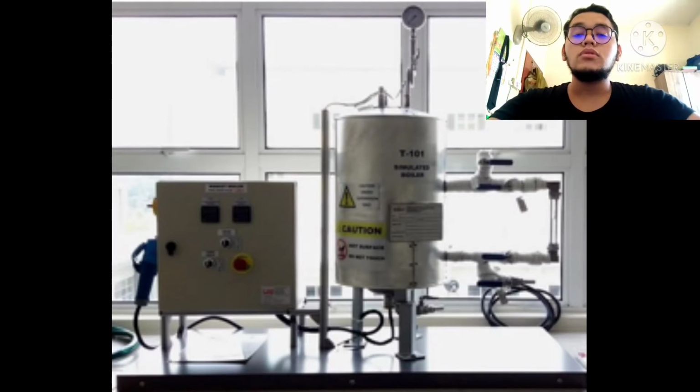For the shutdown procedure, we need to switch off the heater and leave the vessel to cool down until it reaches room temperature. Then we need to switch off the main power supply after the boiler has reached room temperature. We need to retain the water for the next experiment. After that, we open the valve at the upper part of the side glass, the MVB102, to release the water. And lastly, we need to open the valve at the bottom part of the side glass and the valves MVB104 and MVB105 to drain out the water from the tank.